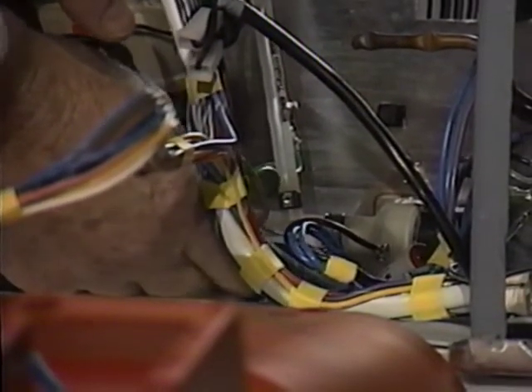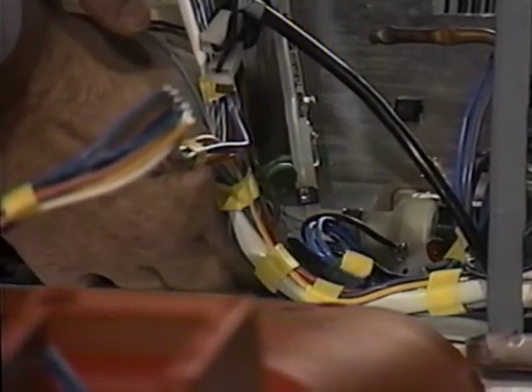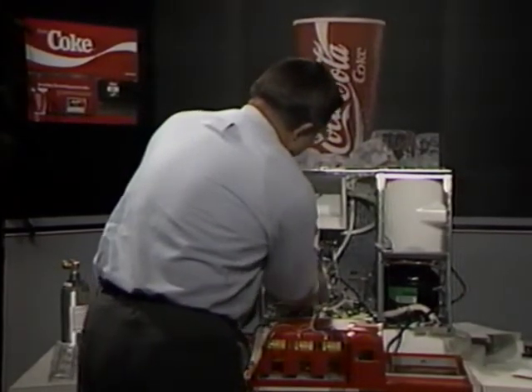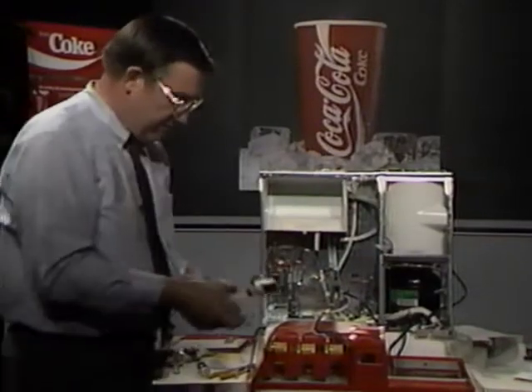There's one right up under the evaporator compartment, the syrup cooling compartment. We take it out, and then there's one below it. And then we break the water line at the double check valve by just taking the nut loose and moving the line out of the way. Now the pump is ready to just lean forward, pull the inlet valve the rest of the way through, and you have it out.